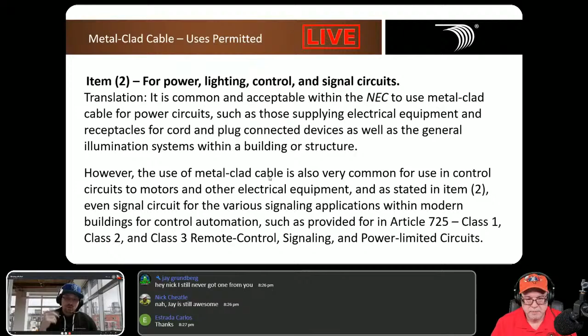We used to run that stuff a lot when wiring up schools—using it for lighting control with the MC and the low voltage 0 to 10 dimming. It helped because the system was set up for the room: when the sun would reflect and you'd get a certain amount of light, it would balance out the room light to match it, including shading. It was really nice to have that 120 volt and the low voltage in just one connection, able to run it together. So I used to do a lot of that in schools.